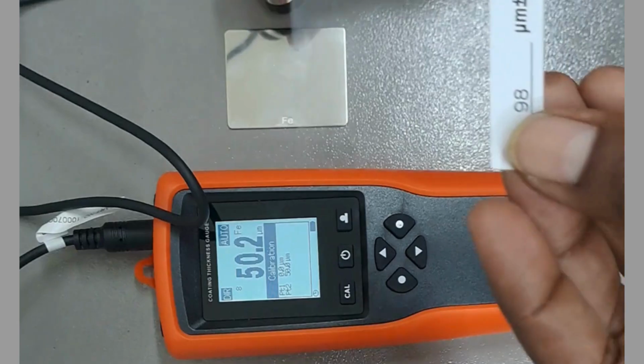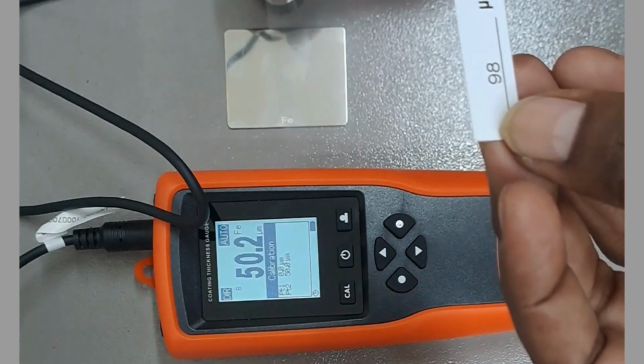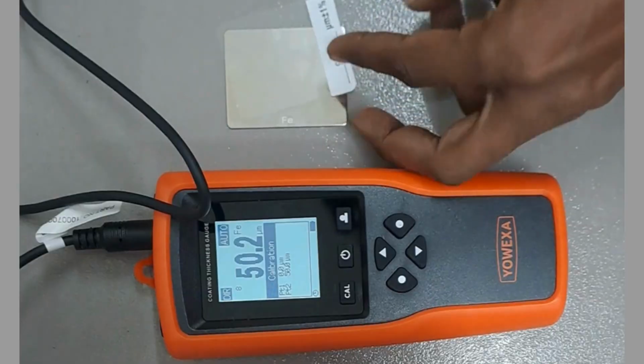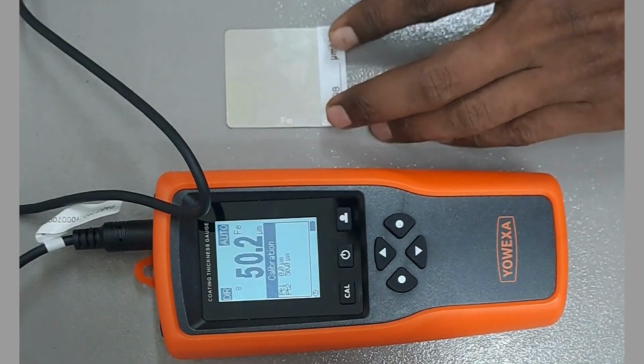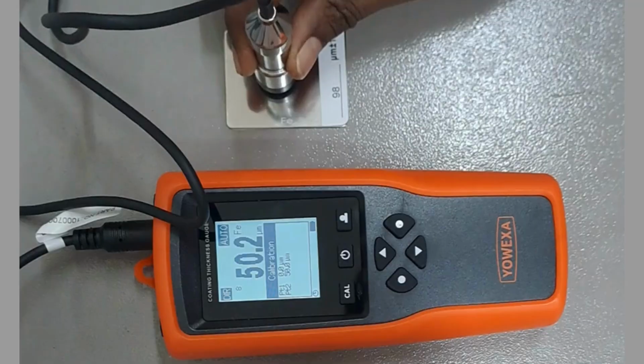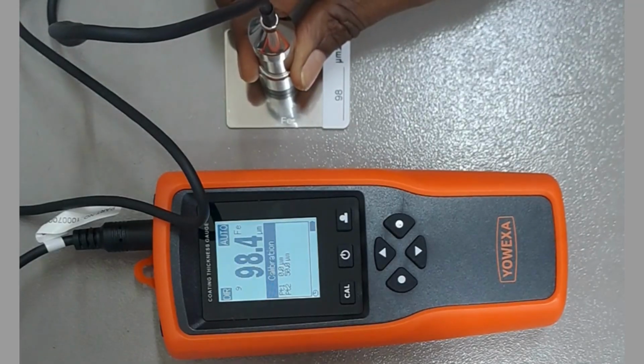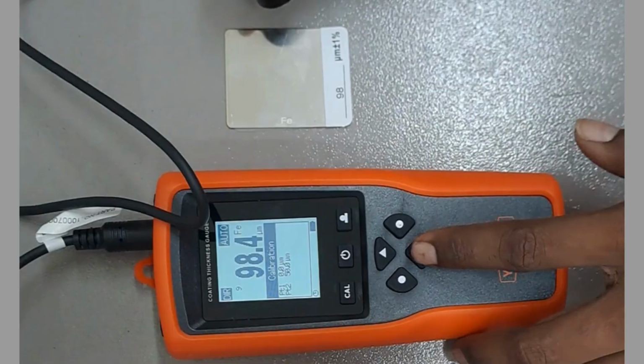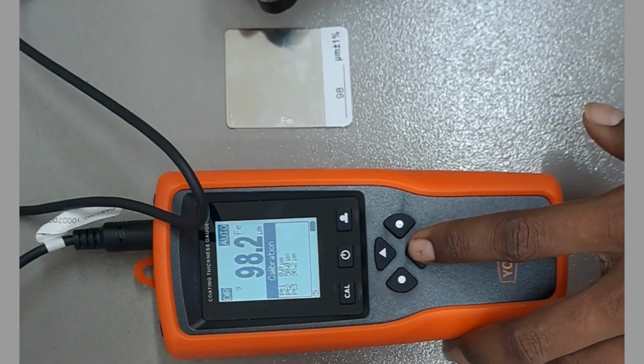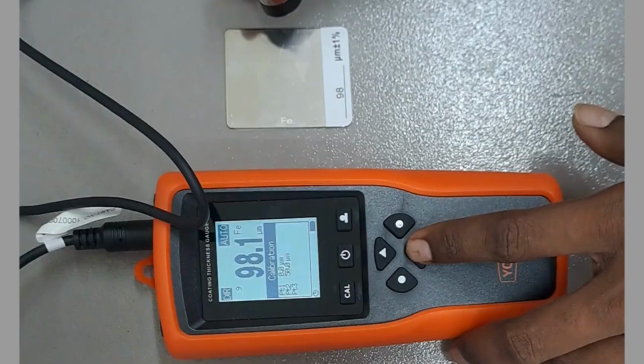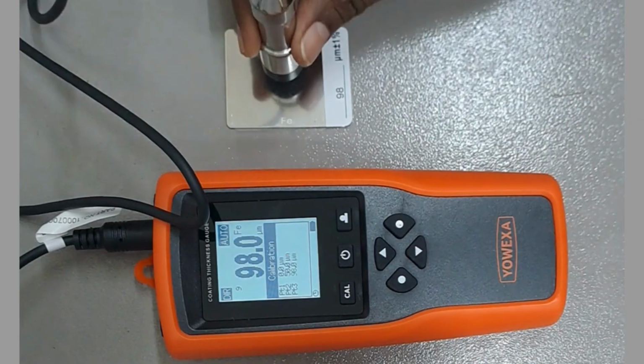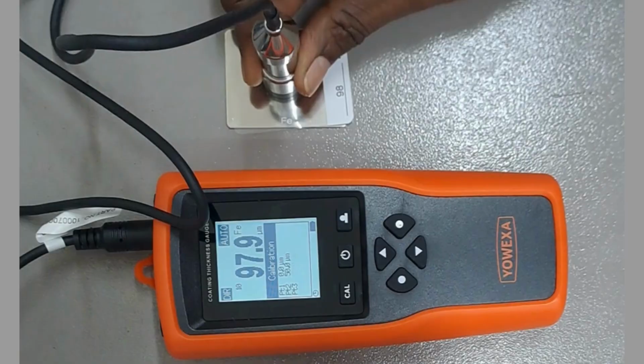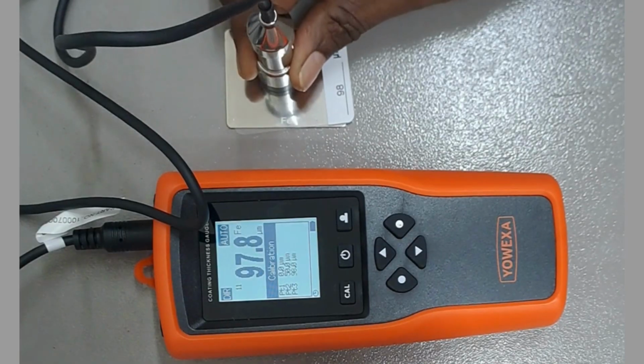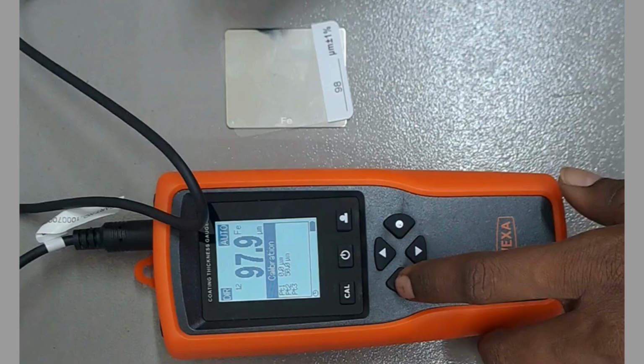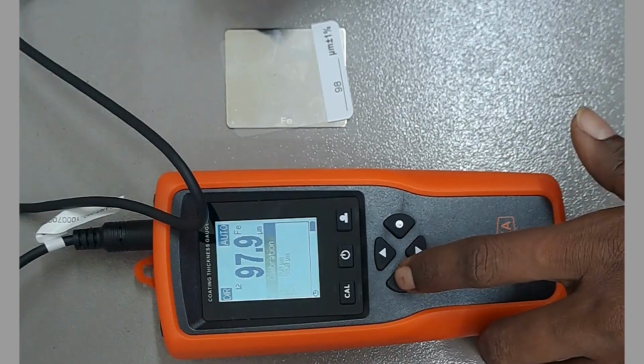Now we will do the third point calibration. We will take 98 micron. Place the probe on the foil and raise it after 1 beep. Okay, it's 98.4. We will adjust to 98.0 exactly. Okay. Now press the left button to confirm the third point calibration.